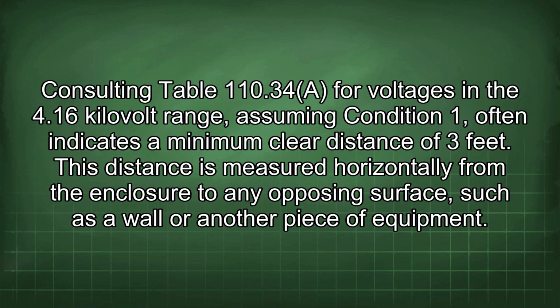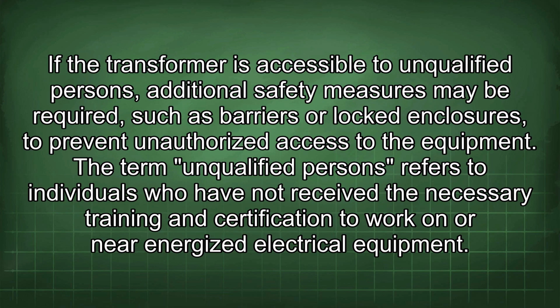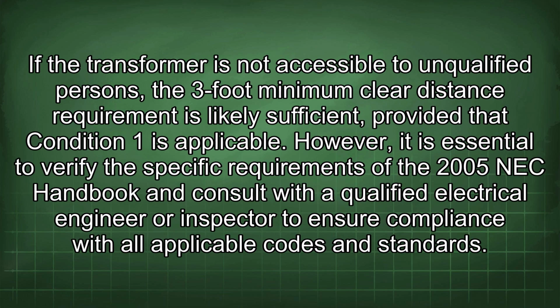enclosure. Consulting Table 110.34 for voltages in the 4.16 kV range, assuming Condition 1, often indicates a minimum clear distance of 3 feet. This distance is measured horizontally from the enclosure to any opposing surface, such as a wall or another piece of equipment. If the transformer is accessible to unqualified persons, additional safety measures may be required, such as barriers or locked enclosures, to prevent unauthorized access to the equipment. The term unqualified persons refers to individuals who have not received the necessary training and certification to work on or near energized electrical equipment. If the transformer is not accessible to unqualified persons, the 3-foot minimum clear distance requirement is likely sufficient, provided that Condition 1 is applicable.